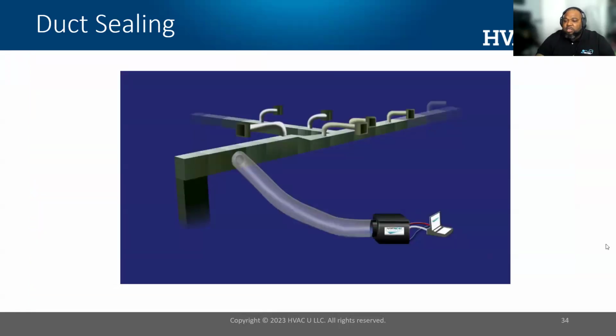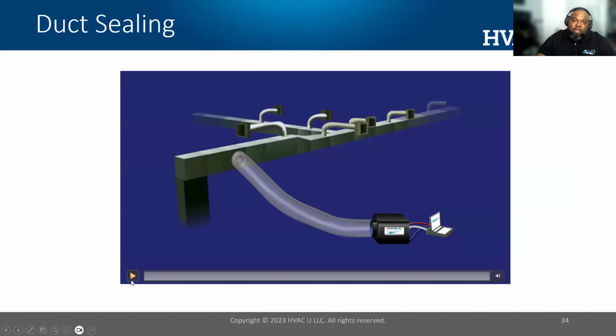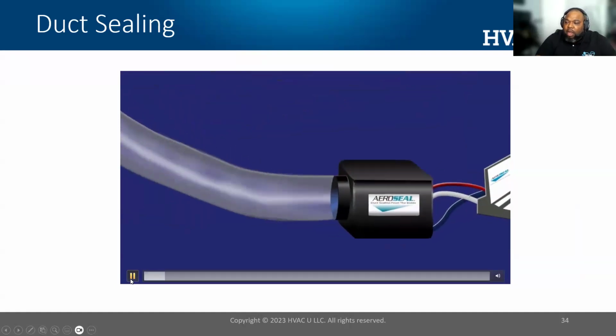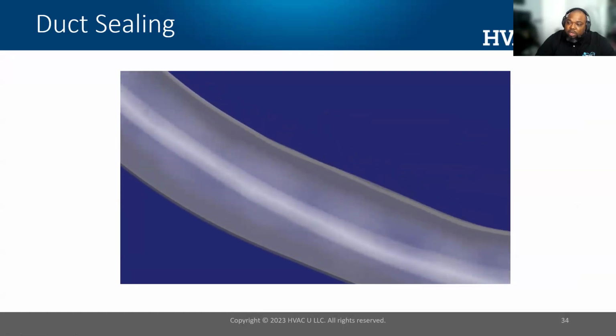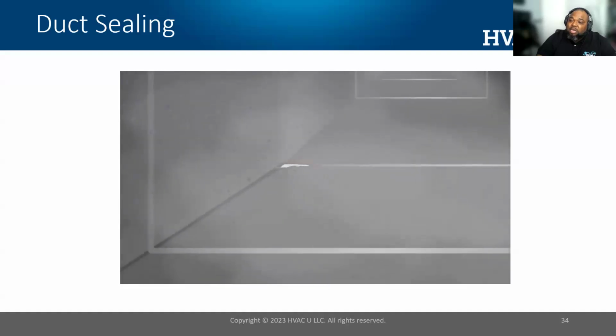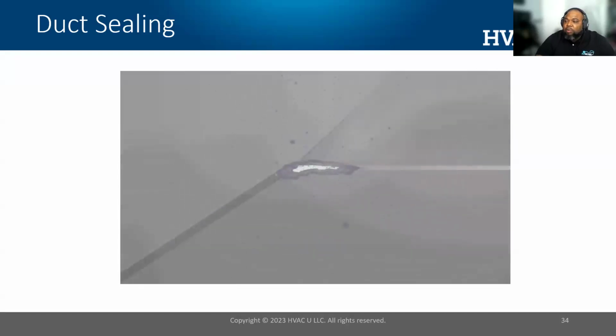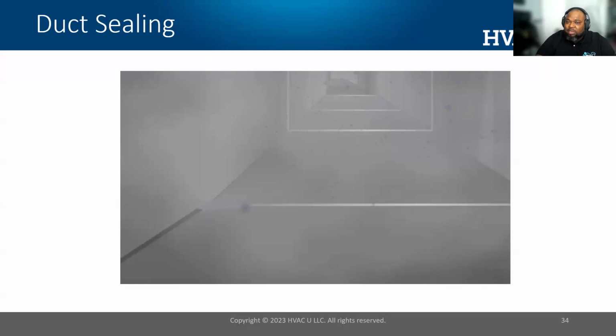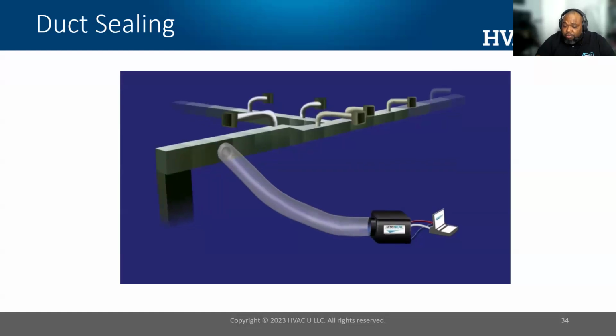One process that we use is to seal ducts using an aerosol inside, typically since we personally work in the retrofit world. One of the aerosol systems that we use is where we inject the duct sealant inside the duct system. As it travels through the duct system, it will find those leaks and seal them from the inside. On the return side of the system, this reduces the likelihood that particles in the attic, such as fiberglass or insects or rodents, or their byproducts, get inside the duct system and make us sick. So this is one way, often many people don't think about, where duct sealing is also very beneficial.